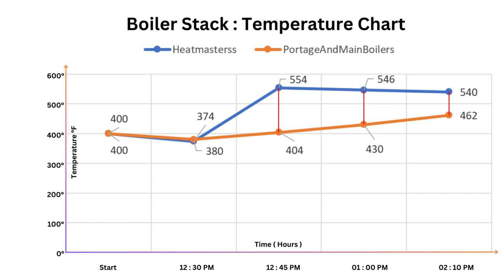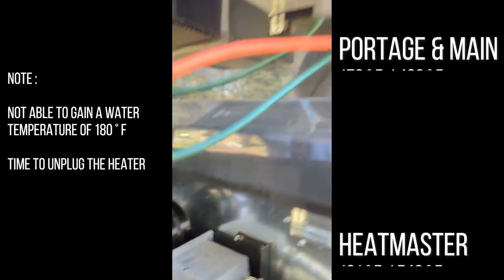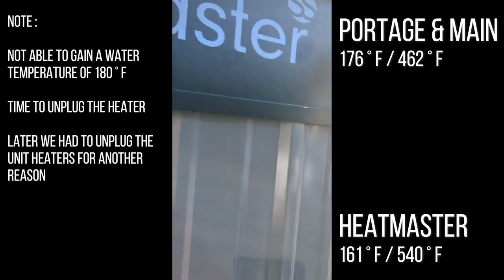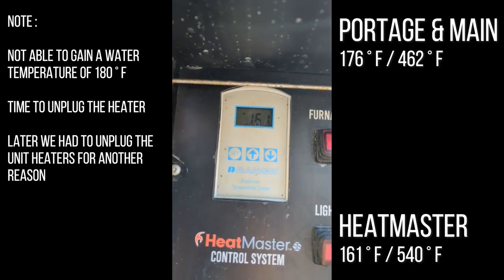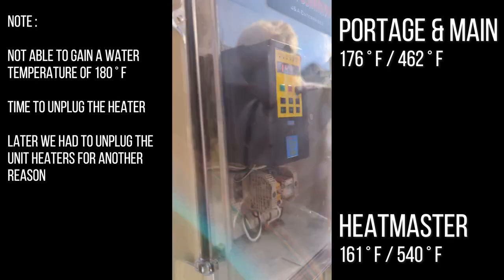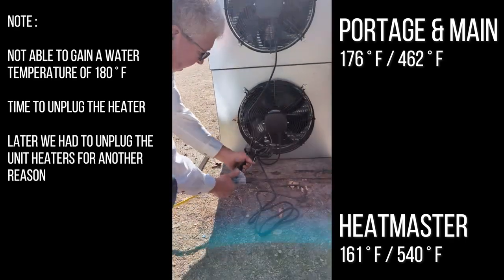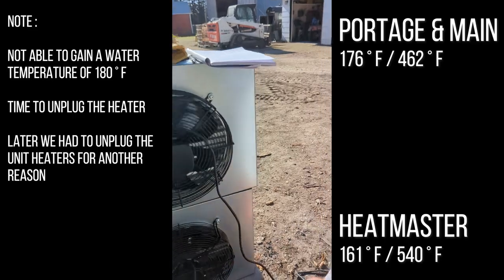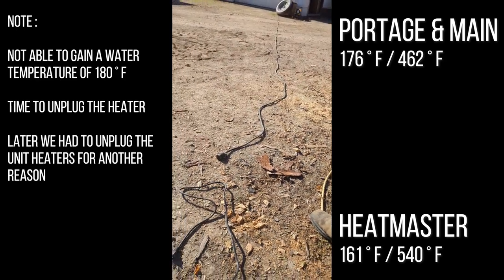Unplugging one heater on each unit will cause the Portage and Main to cycle off shortly. We're still at 176 degrees water and 461 degrees stack on the Portage and Main, versus 540 degrees stack and 161 degrees water on the Heatmaster — it was set at 180 and has dropped 19 degrees. We're going to unplug the bottom unit heater on both the Heatmaster and the Portage and Main to let the Heatmaster catch up.